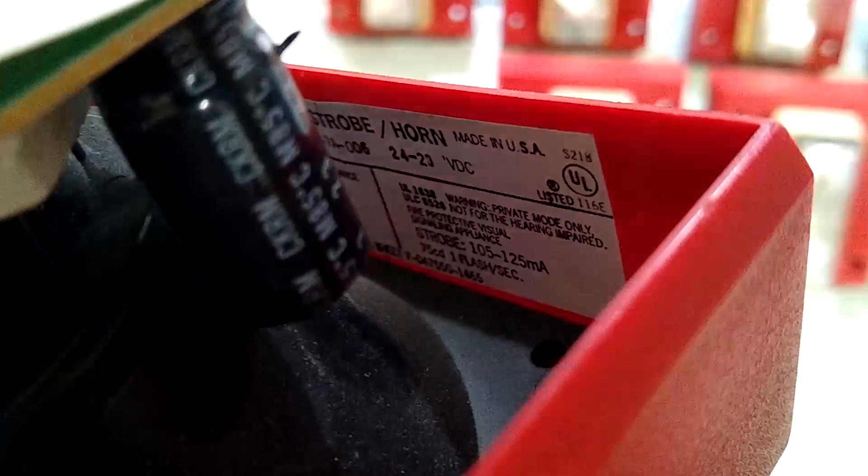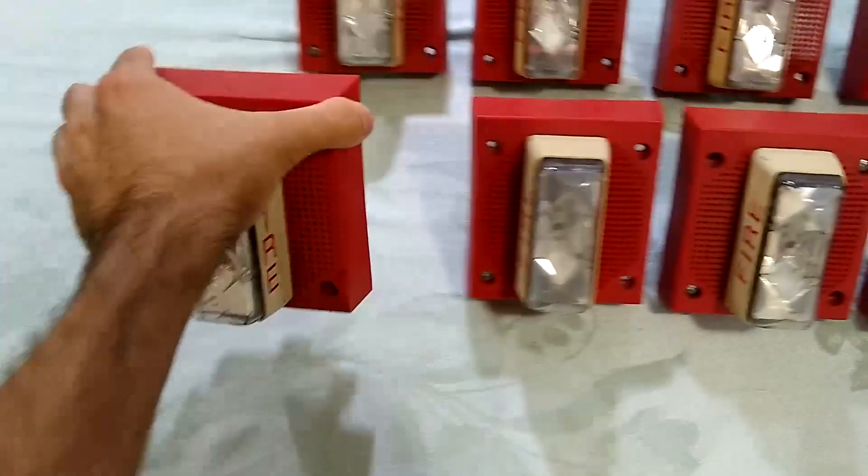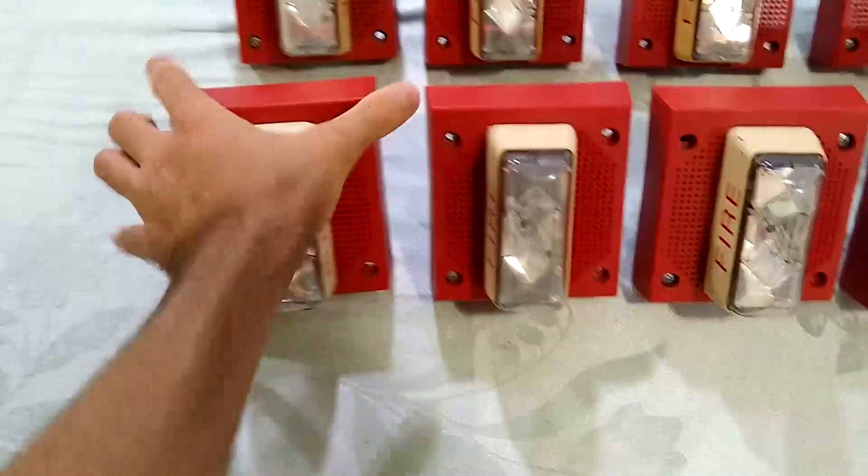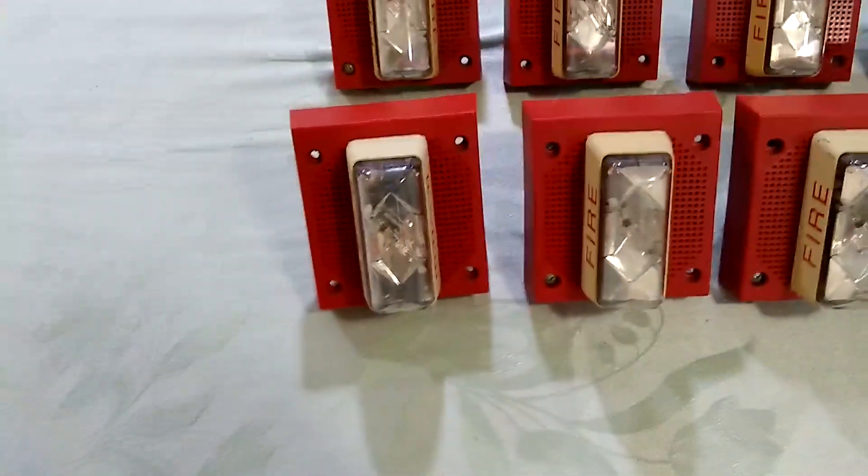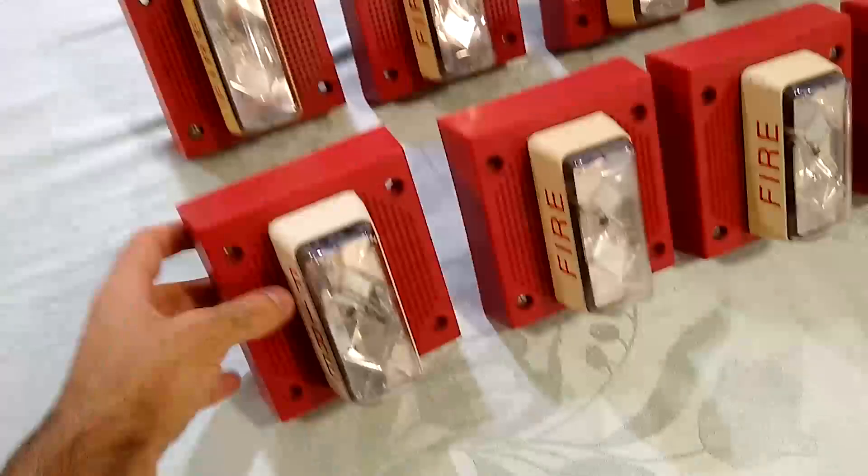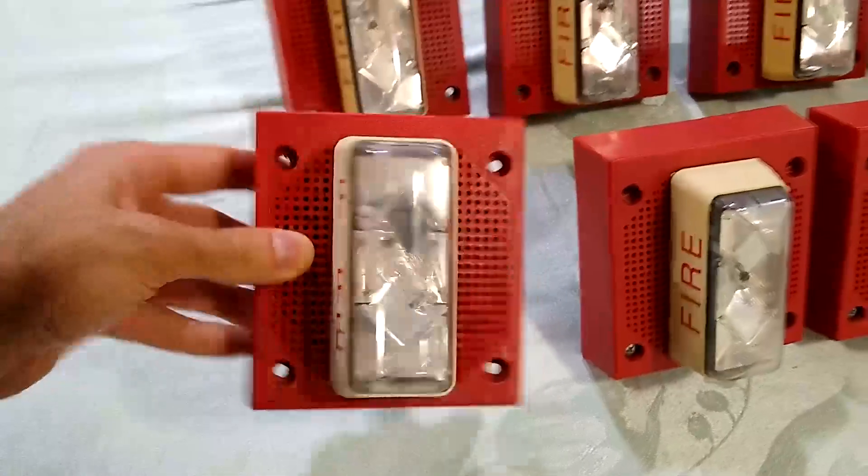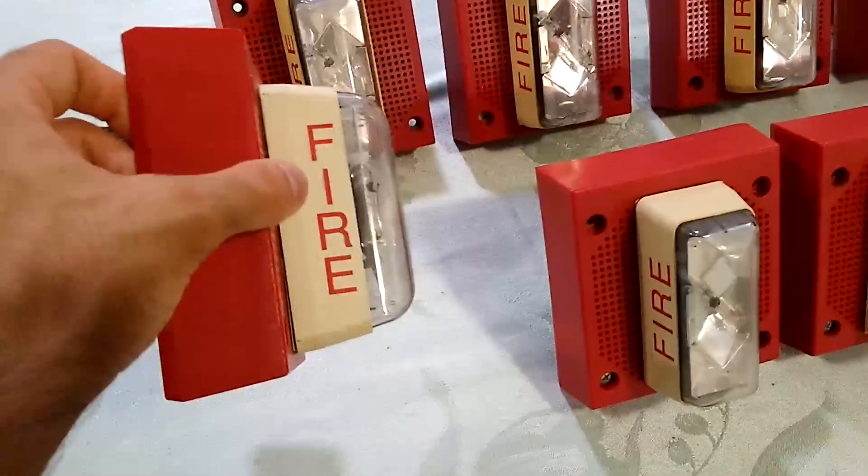Somewhere, I don't know if you can see it there. And warning, private mode only, not for the hearing impaired. So I think Edwards should have made up its mind. But it's rated both for 15 and 75 candela, which usually means that it's 75 candela when viewed from the front, and 15 candela when viewed from the side.